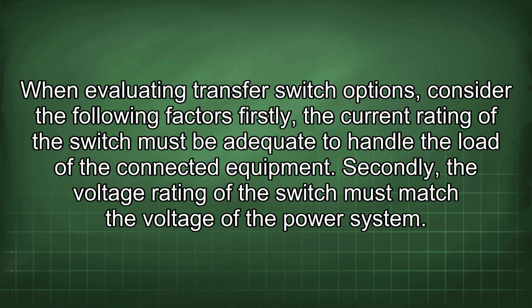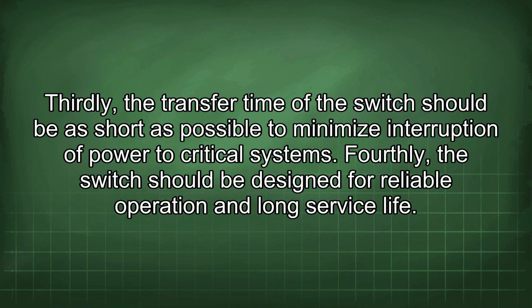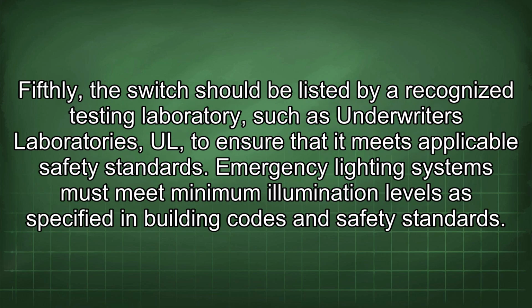When evaluating transfer switch options, consider the following factors. Firstly, the current rating of the switch must be adequate to handle the load of the connected equipment. Secondly, the voltage rating of the switch must match the voltage of the power system. Thirdly, the transfer time of the switch should be as short as possible to minimize interruption of power to critical systems. Fourthly, the switch should be designed for reliable operation and long service life. Fifthly, the switch should be listed by a recognized testing laboratory such as Underwriters Laboratories, to ensure that it meets applicable safety standards.